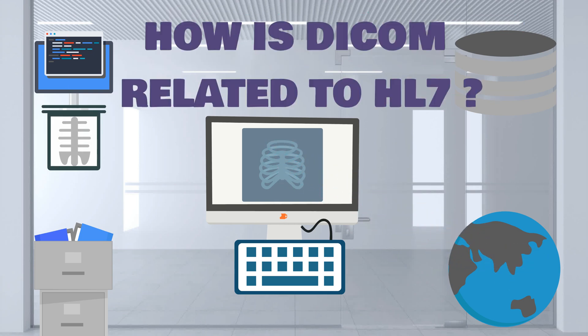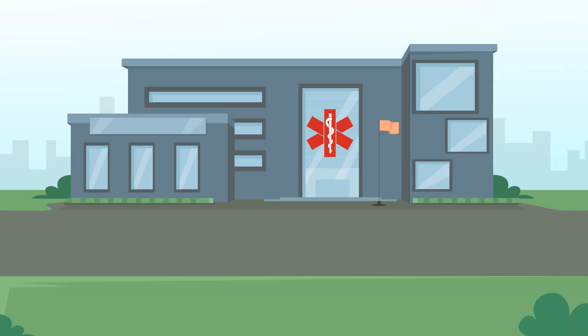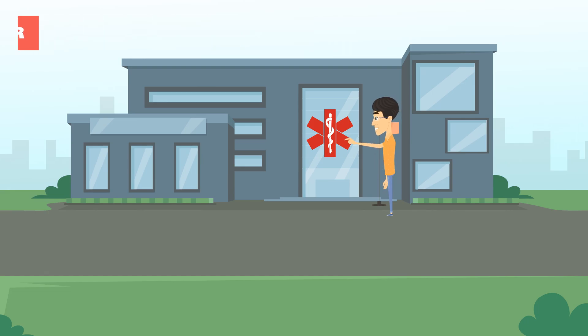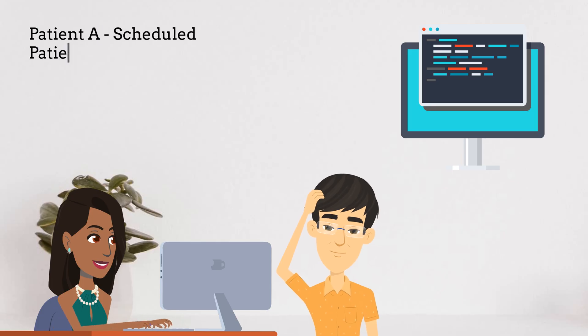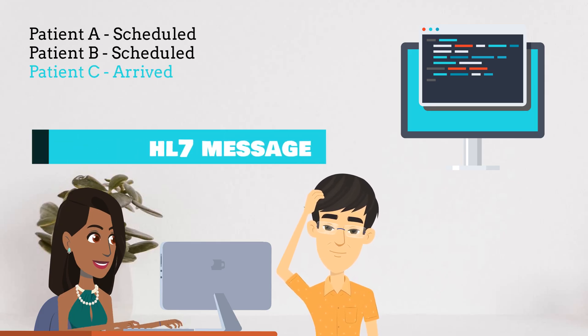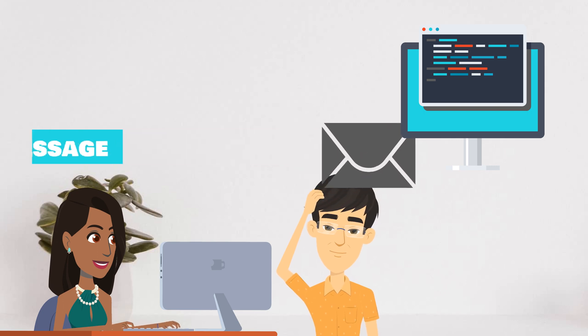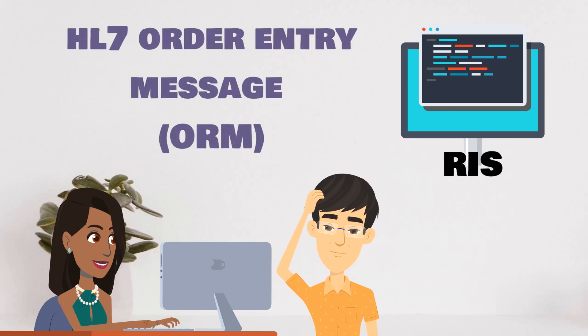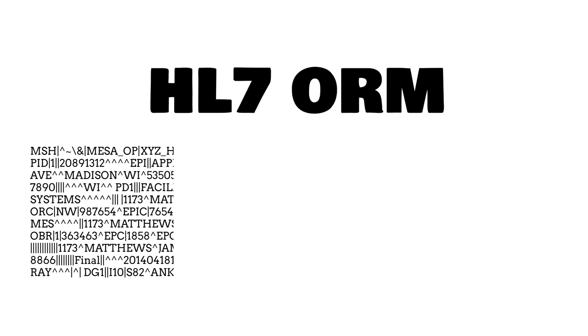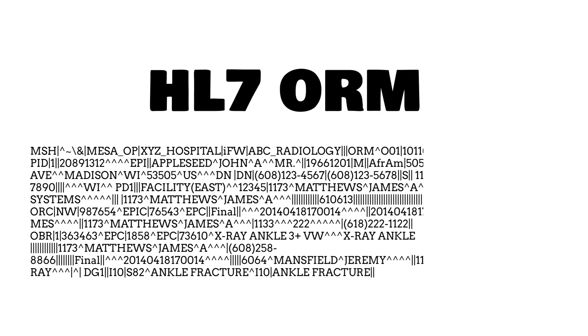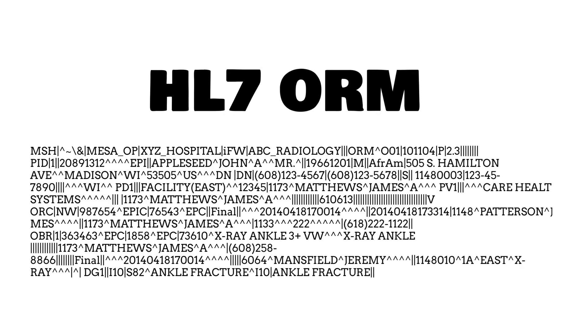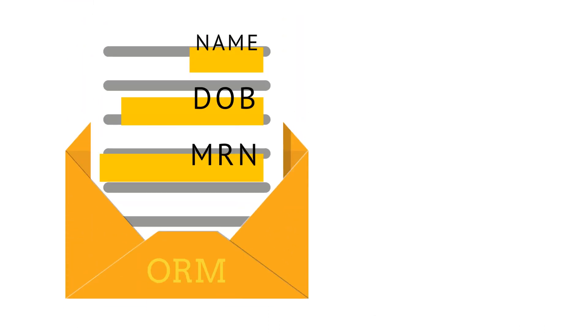How is DICOM related to HL7? A patient can be checked in to their MRI appointment when they arrive at an outpatient imaging center. A physician must place an order for the MRI exam, which is sent to the Radiology Information System. This is called an HL7 order entry message, called an ORM. The HL7 message will contain important patient identifiers such as name, date of birth, and medical record number.